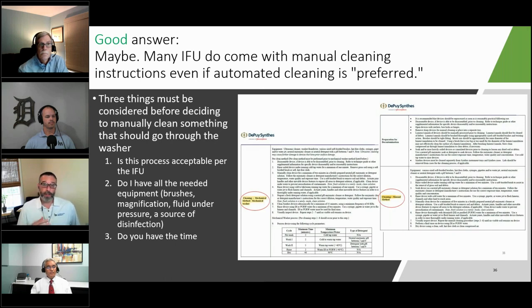If you don't see manual and an automated, you may not have a choice, right? We say to follow the IFU, and if it says mechanical cleaning or automated cleaning and nothing else, then just assuming that scrubbing it in your hand wash sink works is a bad assumption. So if you're going to do this, here are the things I want you to consider. The 3 biggest things would be, 1, is it acceptable per the IFU?